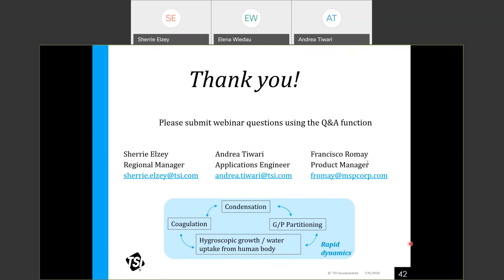Is nicotine polluting the instrument and does it need particular treatment for cleaning? No — these instruments are built to characterize aerosols. If the aerosol contains nicotine, it contains many other things as well, and the instrument will handle and size it appropriately, with material ending up on a filter within the instrument. Regarding cleaning, diagnostic criteria in the manual or maintenance guide can advise you on whether cleaning is warranted based on the instrument's symptoms.